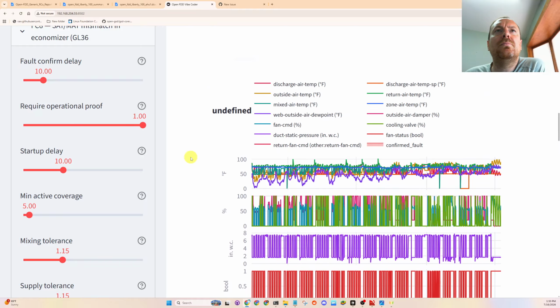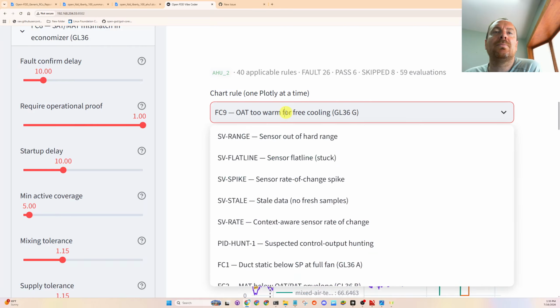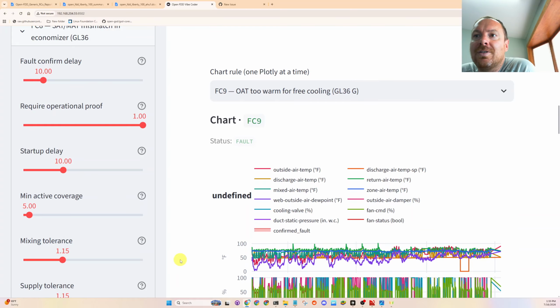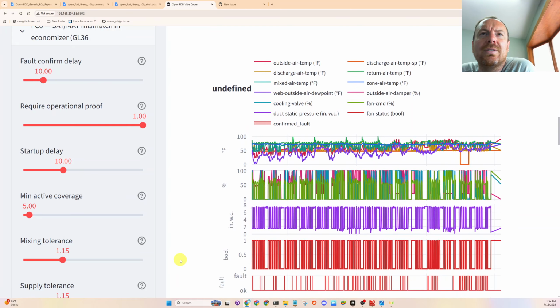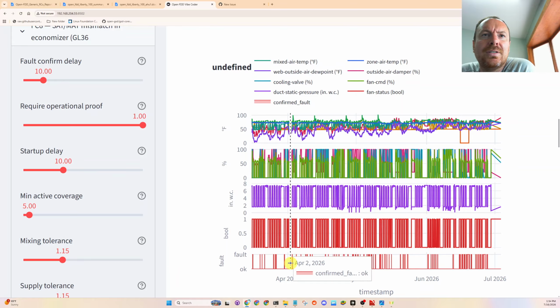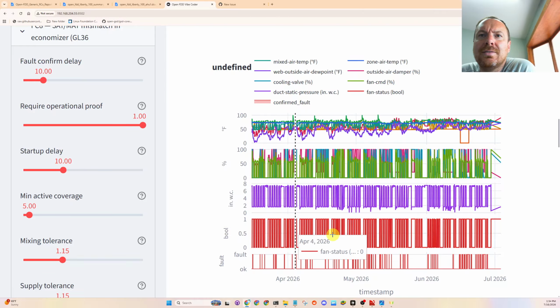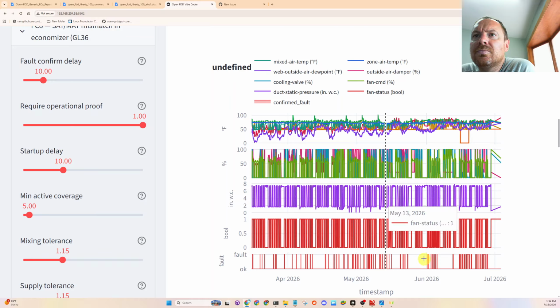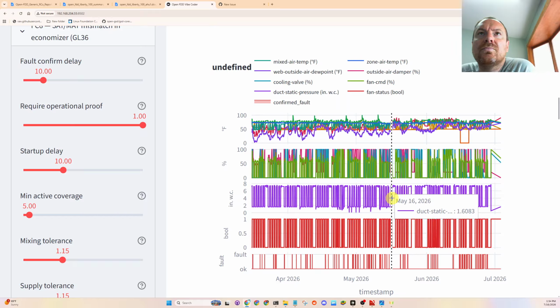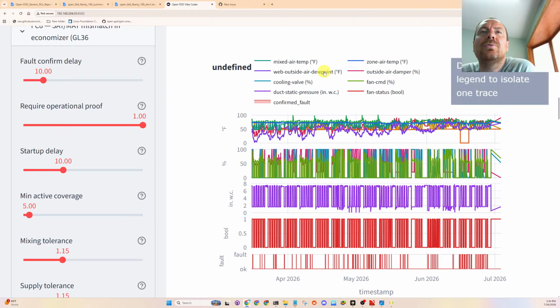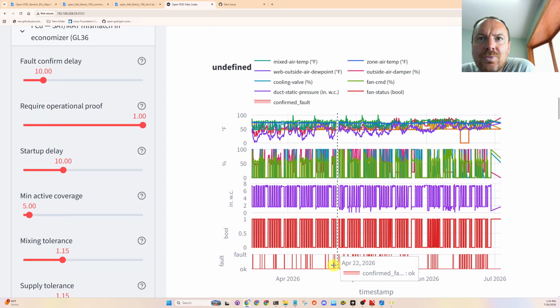Okay, so we just have to drop down. Shoot, another one we should look at next. These fault conditions 8, 9, 10, they're all to do with free cooling. Oh boy, we have a lot of data to look at here. So faults, bool. So this is, I think, fan status. Okay, so we have outdoor air dew point on here too, which I wanted to view. So let's just zoom in on the fault.